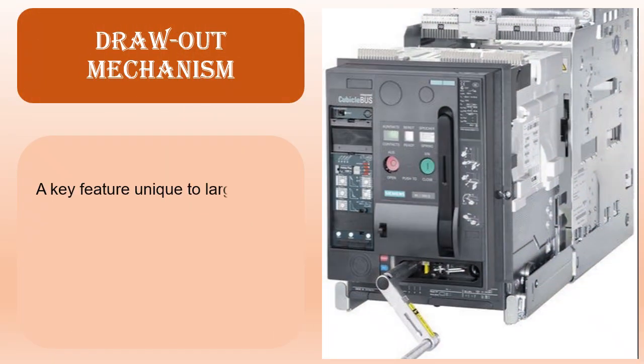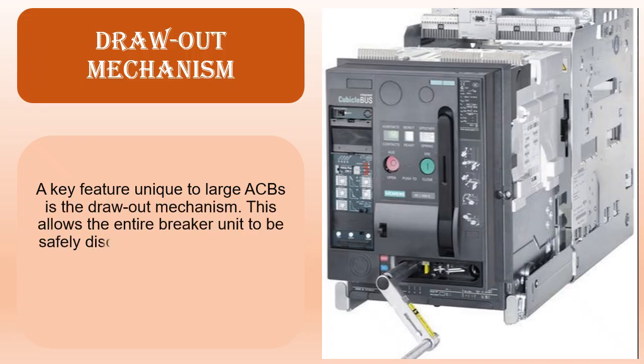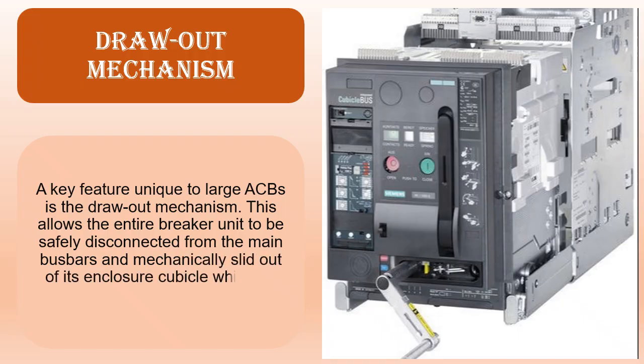Draw-out mechanism. A key feature unique to large ACBs is the draw-out mechanism. This allows the entire breaker unit to be safely disconnected from the main bus bars and mechanically slid out of its enclosure cubicle while the main system remains energized.